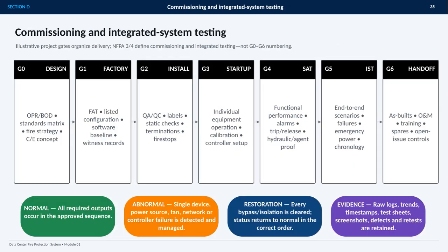This slide organizes commissioning and integrated system testing into illustrative project gates, from design through handoff. The G0 design gate confirms the owner's project requirements, basis of design, standards matrix, fire strategy, and controls and electrical concept. G1 covers factory activities, including FAT, listed configuration, the software baseline, and witness records. G2 verifies installation quality, labeling, static checks, terminations, and fire stops. G3 is startup, where individual equipment is operated, calibrated, and configured. G4, or site acceptance testing, demonstrates functional performance, alarms, trip and release sequences, and hydraulic or agent performance.